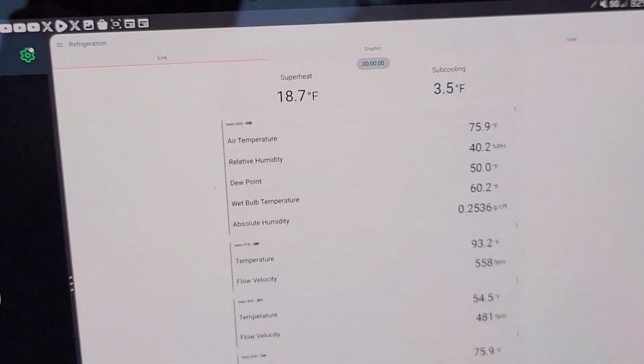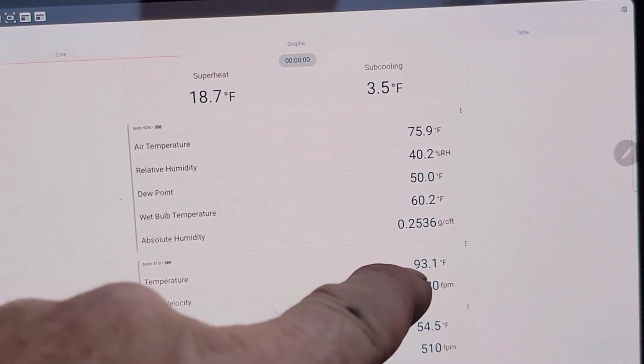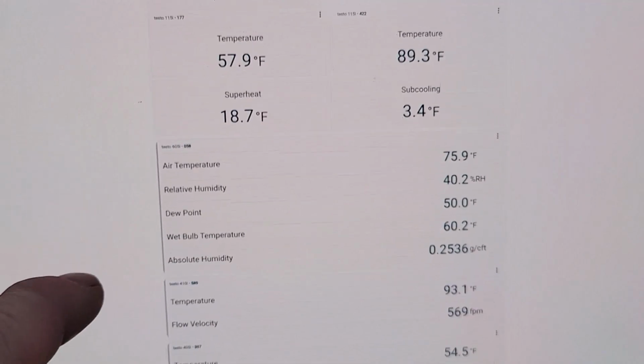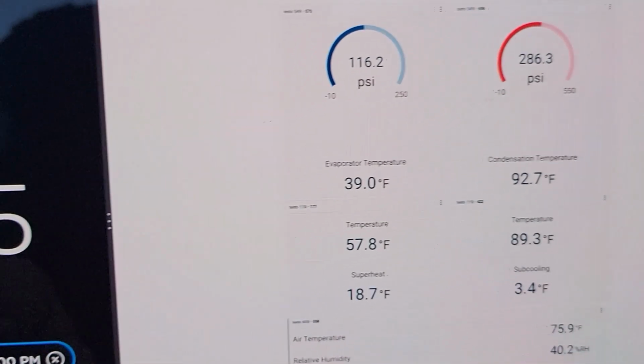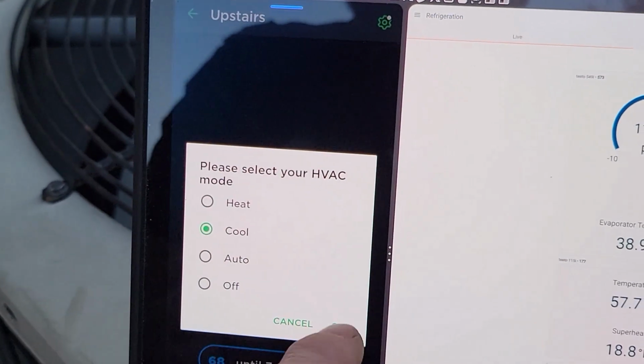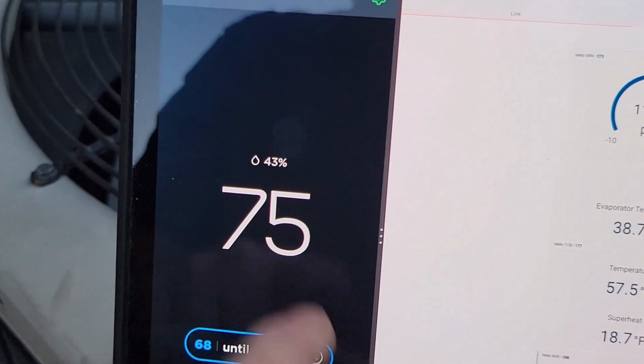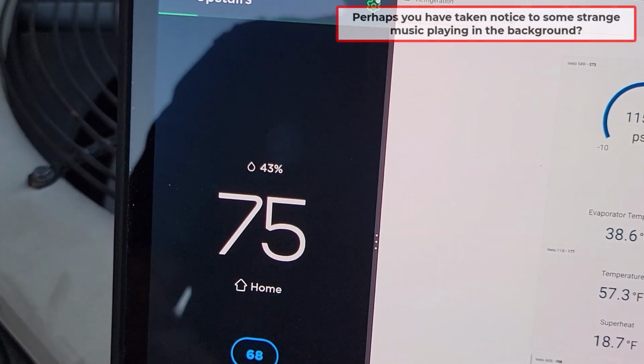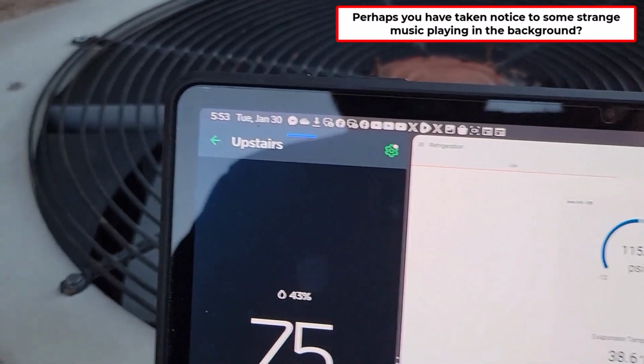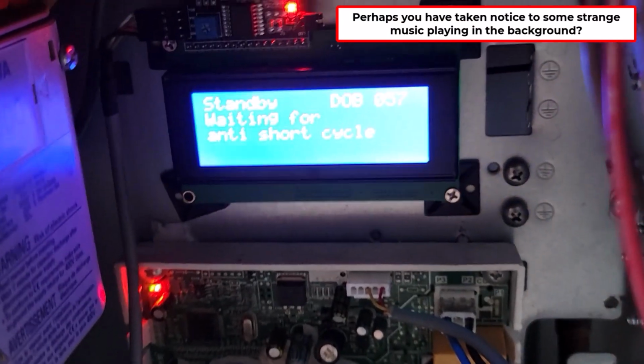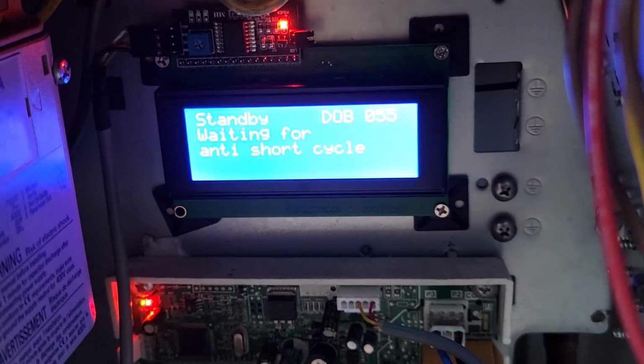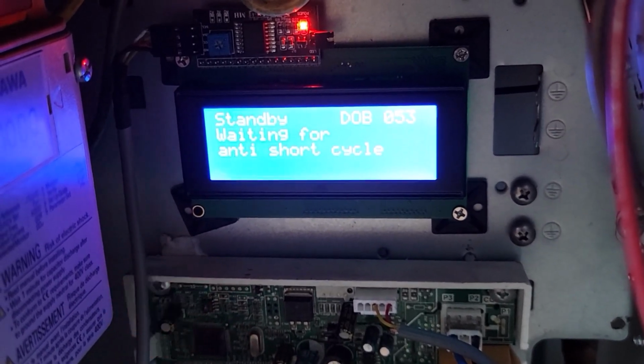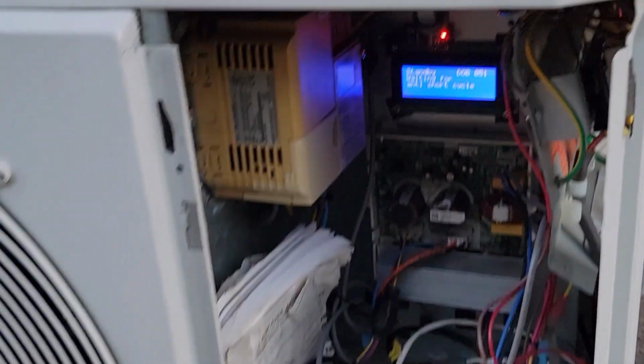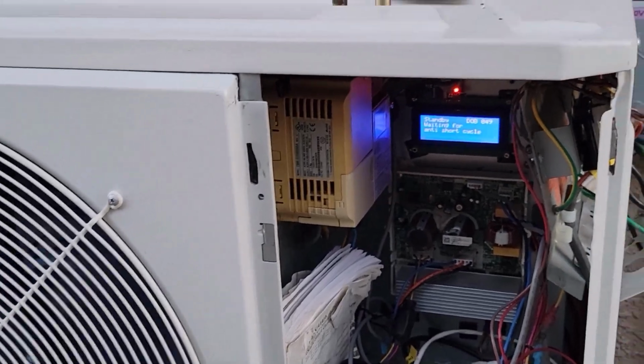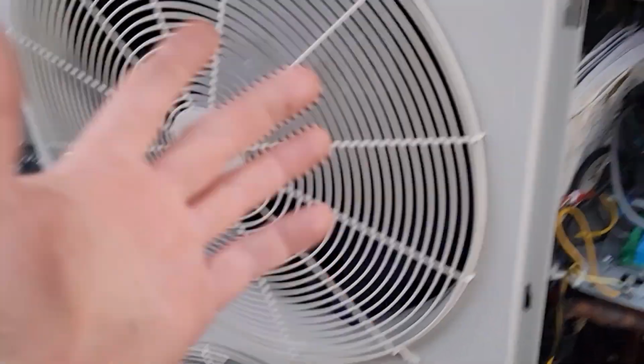So 21 degrees split. It's blowing out 93 degrees out here. We're going to see that in cold air here in a few minutes. So what you're going to do now is we're going to go to this. Oops. First I'm going to hit cancel. And you see it's going to stop. There goes that interrupt on change. It just said standby. Stop, delay on break. Got a minute there. Really only need a minute because I'm running a 3-phase variable frequency drive unit. So the fan stopped. Just taking down that delay on break.